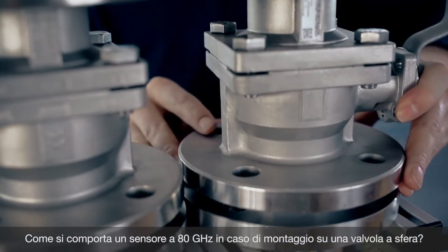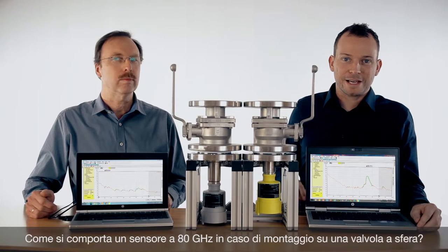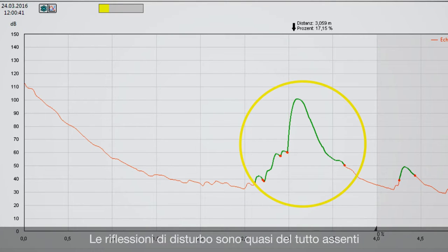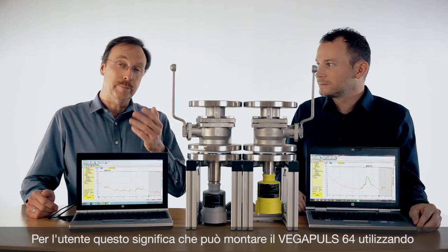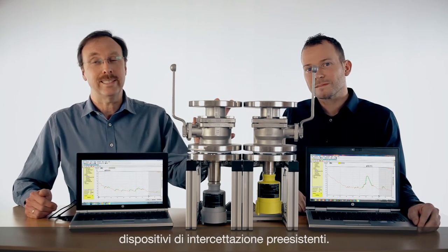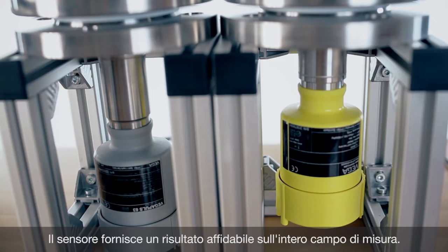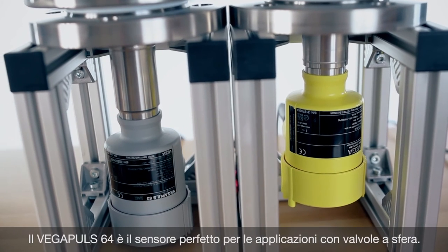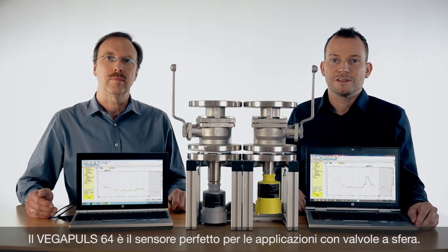On this side we also put a ball valve on top of the VEGAPULS 64. We have a look at the echo curve. You see there is a slight change in the signal but there is not a big problem for the sensor. It does not get false reflections and it still has a very nice product echo to measure. This means for your application it is possible to use existing ball valves and you get very high reliability over the complete measuring range. So the VEGAPULS 64 is the perfect sensor for your ball valve applications.